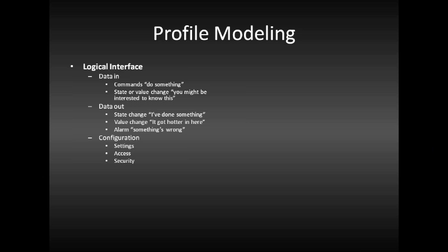And this is all done through configuration. Being able to set these different set points, alarm points, being able to determine who gets to access this information and what kind of security is around this information. If it's something that needs to be authenticated or something that needs to be encrypted, for example. All of that information should be field adjustable, not necessarily put out or put into the device at the time of manufacture.